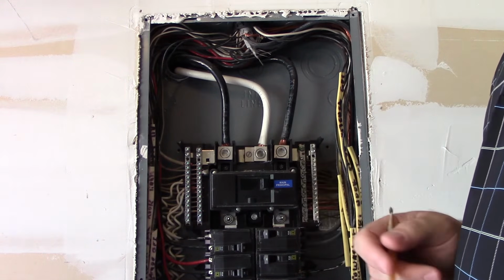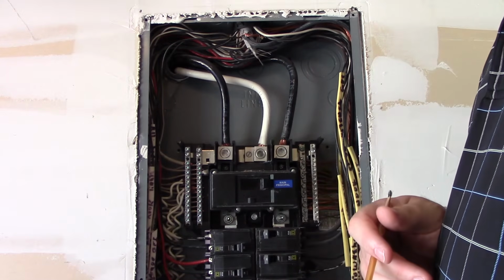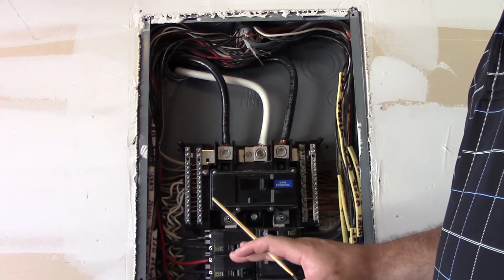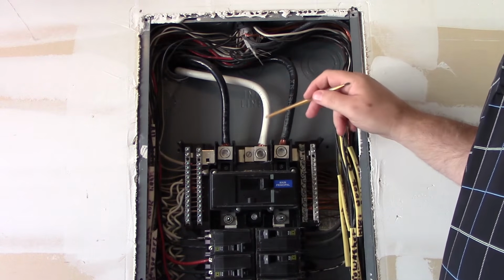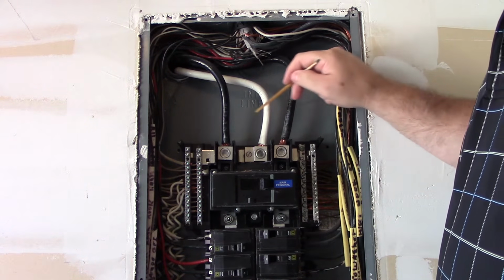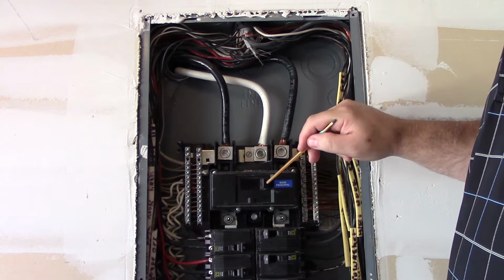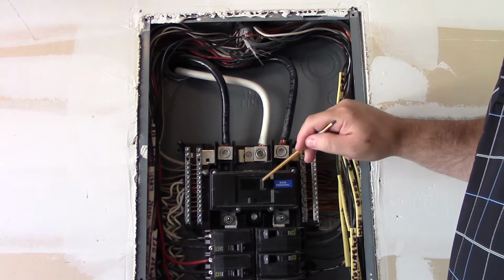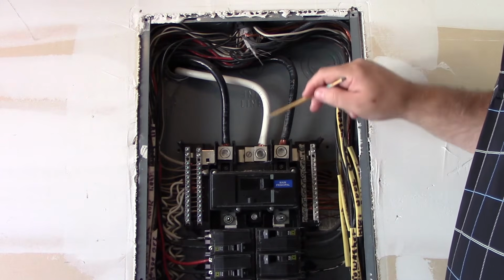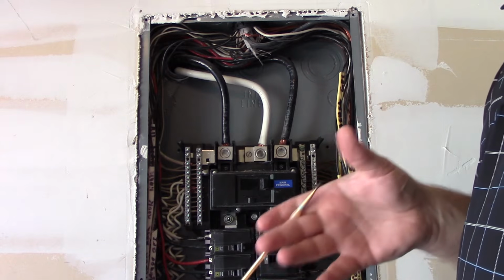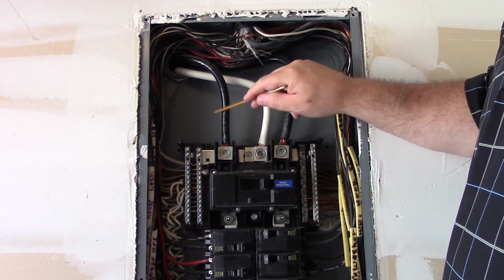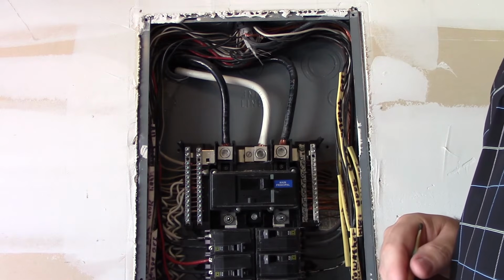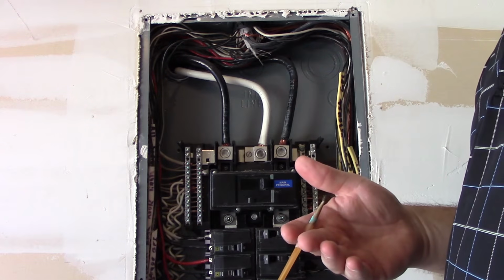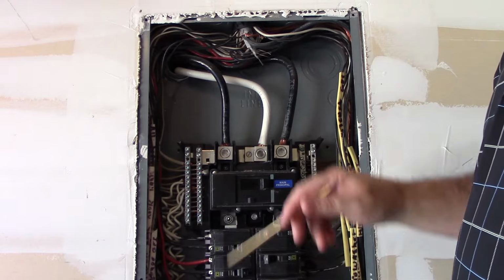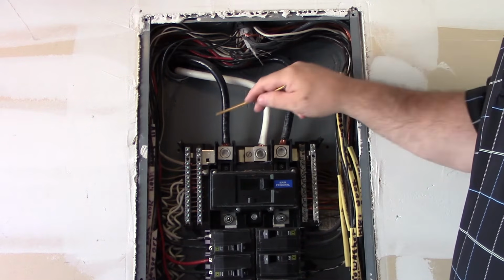For example, under 310.15(B)(7) of the National Electrical Code, if this panel handles 100% of the load, then I can use that table, and basically these conductors have to be at least the ampacity value of 83% of the rating here, and this is a 200 amp rating right here. So these have to be at least that. Now, if you had the old National Electrical Code back in 2008, you had a little table there, and that little table said that this 2/0 copper is good for 200 amps. Now, under 310.15(B)(16), which is your normal ampacity table, you're going to see that it's not. It says it's good for 175 amps.